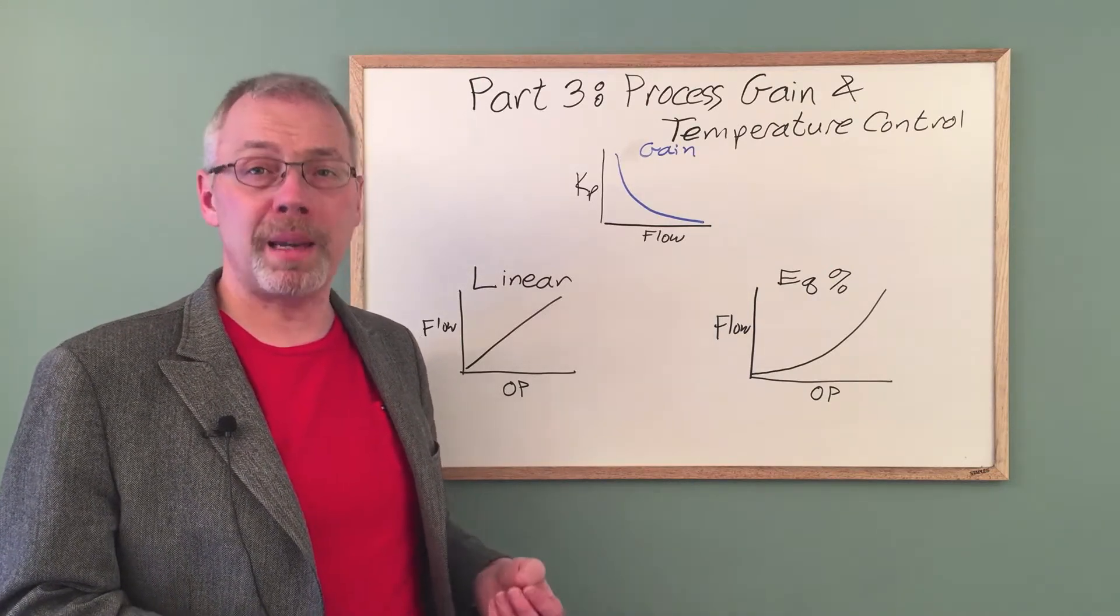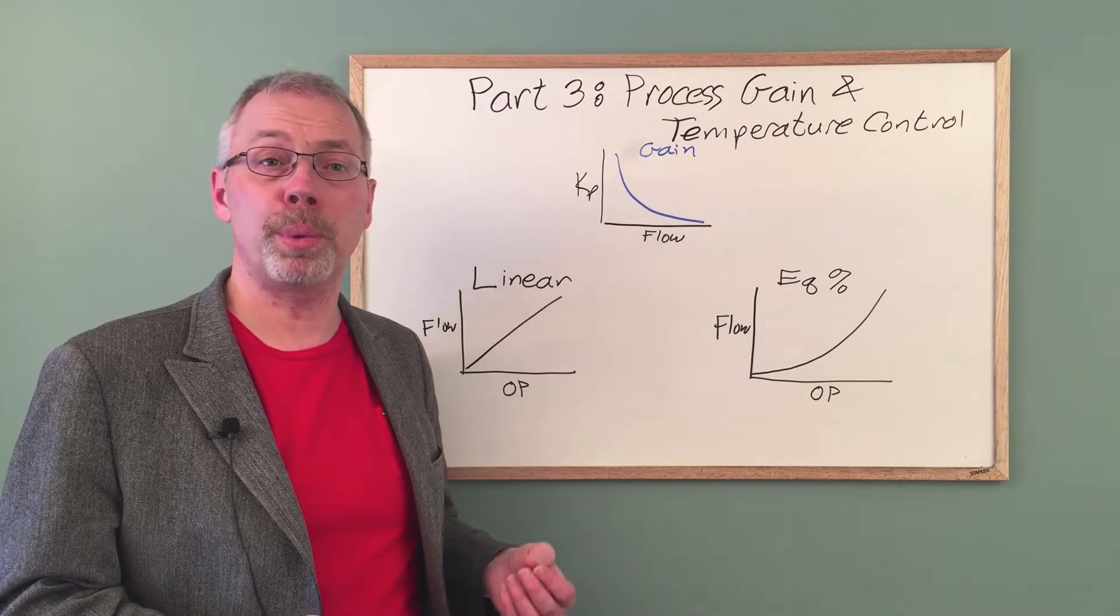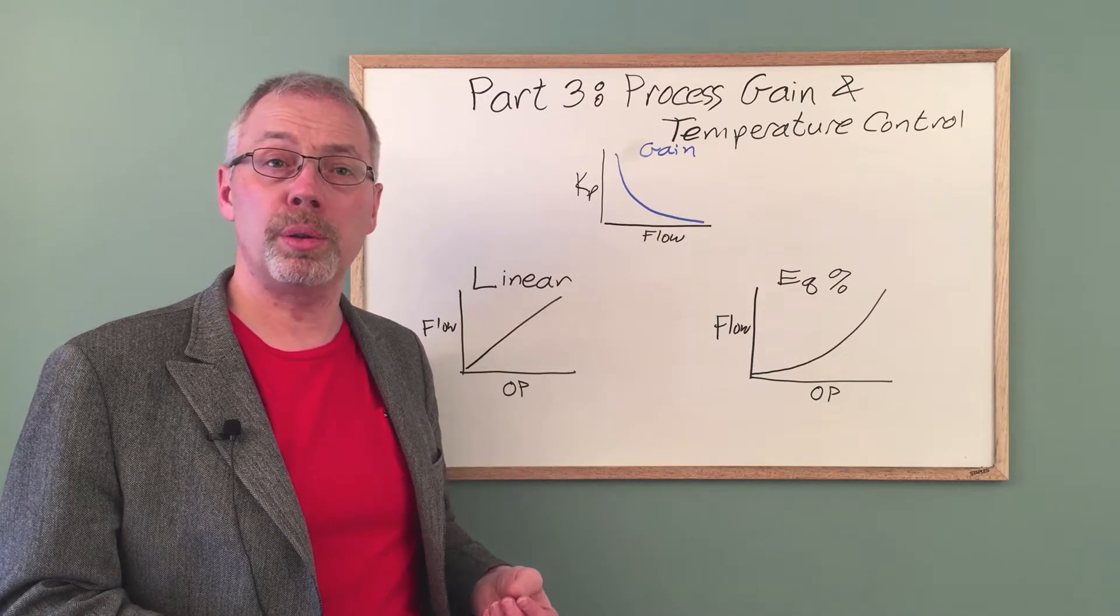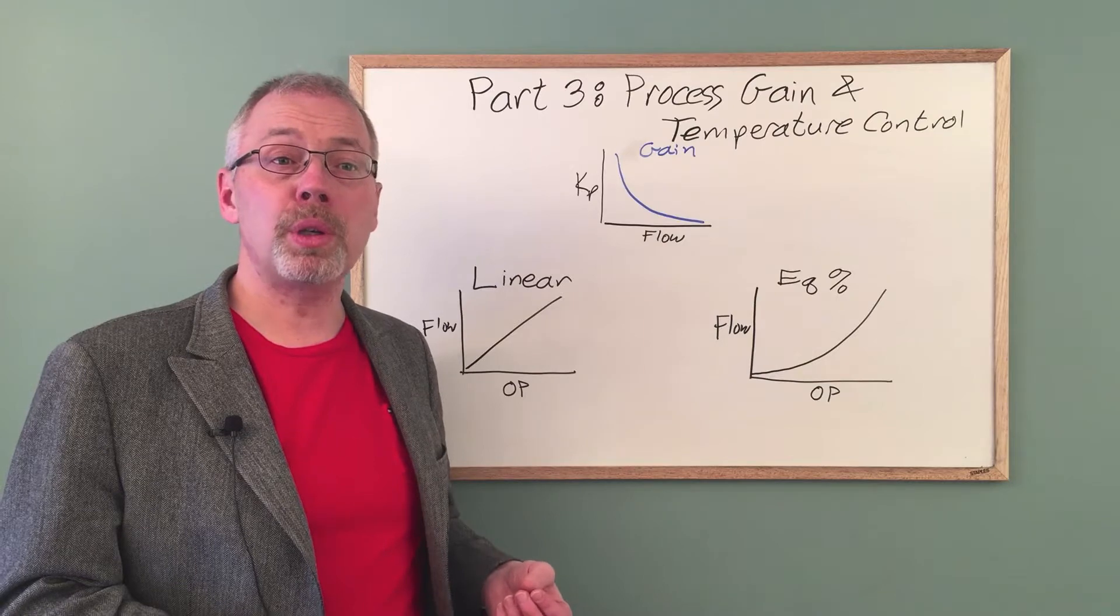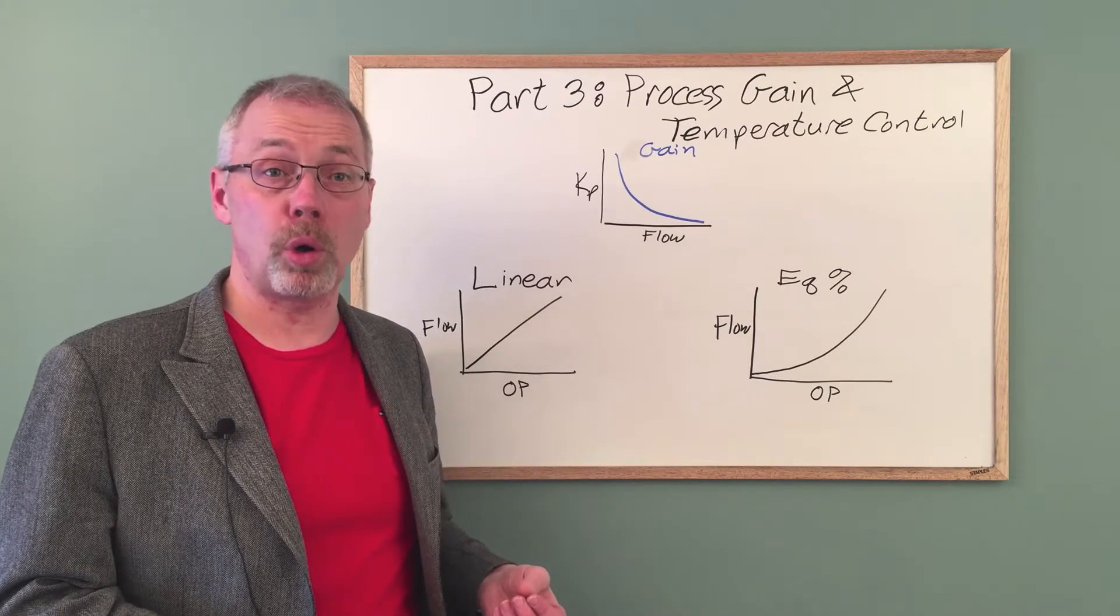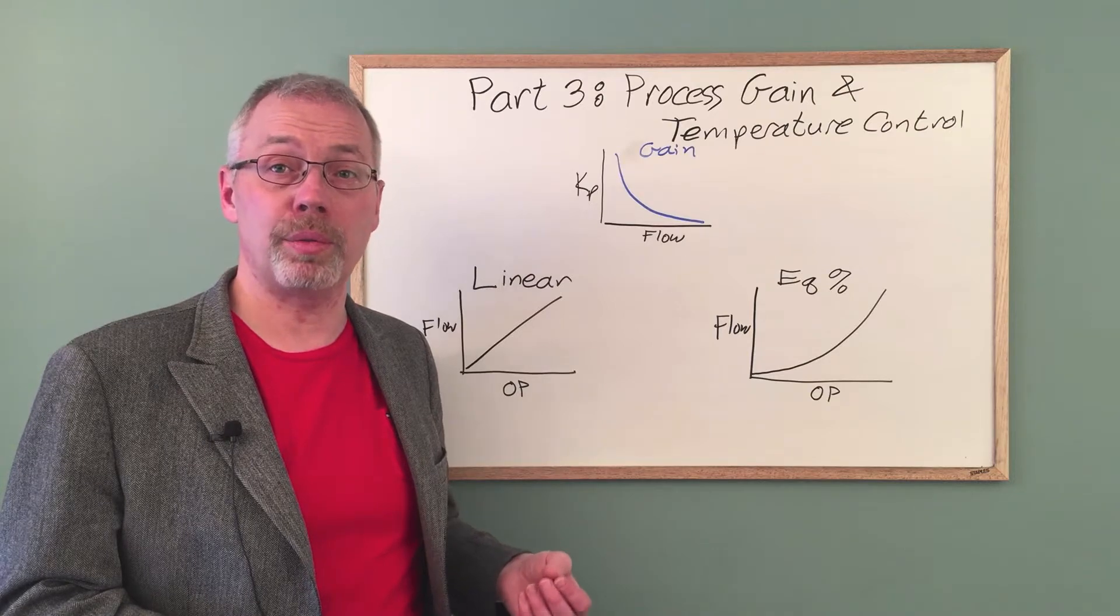What is the benefit? Let's compare temperature control with linear and equal percent valves where the controller is tuned to work well at normal rates. Then we will turn the flow down to one third of normal. This will cause the process gain to increase by a factor of 3.